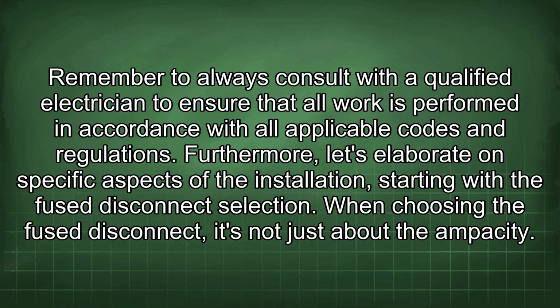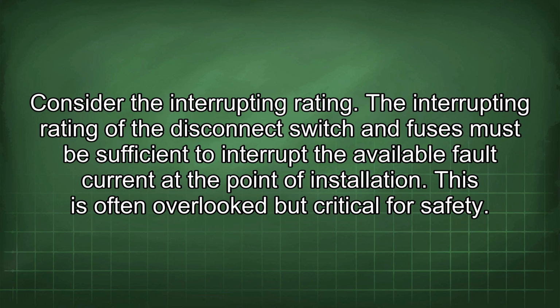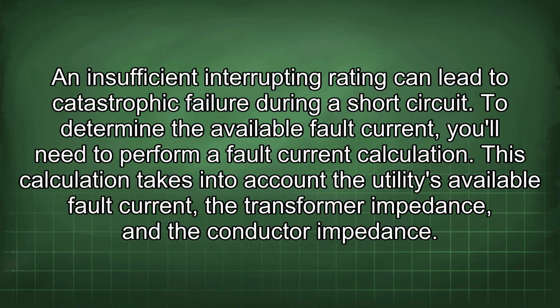When choosing the fuse disconnect, it's not just about the ampacity. Consider the interrupting rating. The interrupting rating of the disconnect switch and fuses must be sufficient to interrupt the available fault current at the point of installation. This is often overlooked but critical for safety. An insufficient interrupting rating can lead to catastrophic failure during a short circuit.